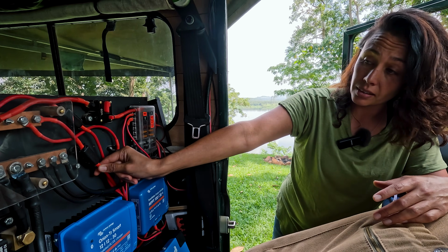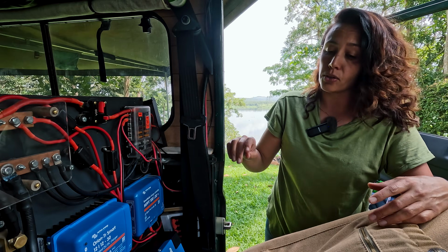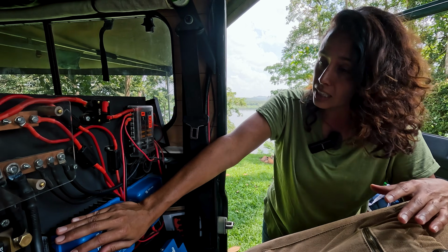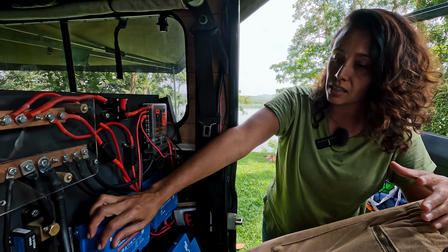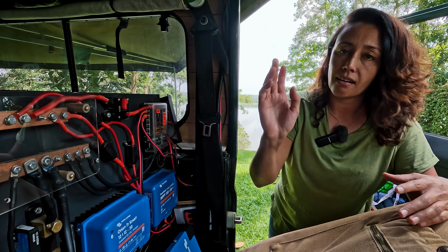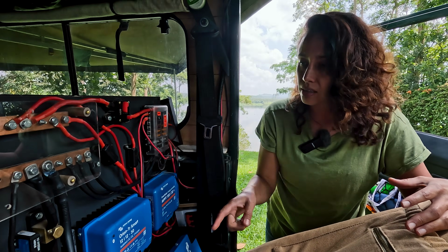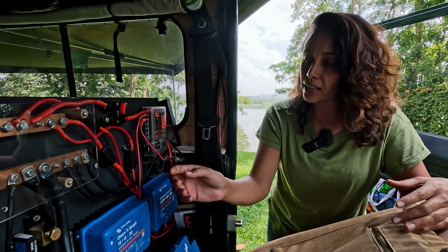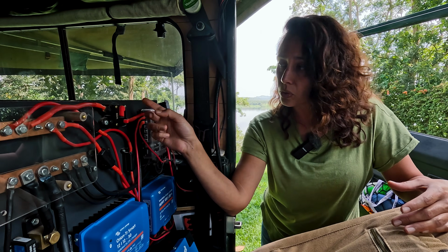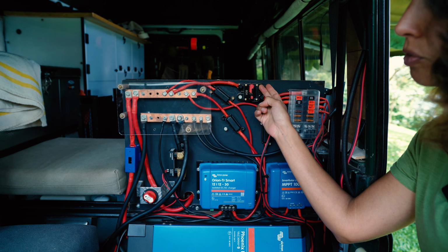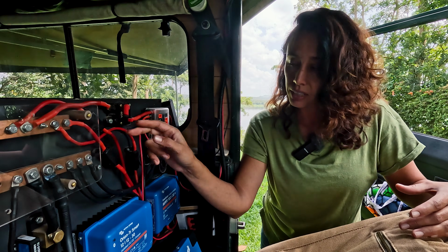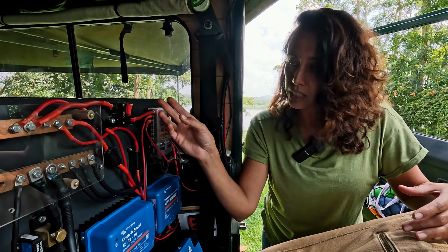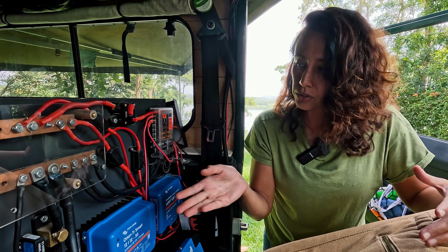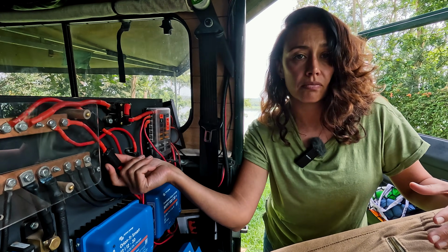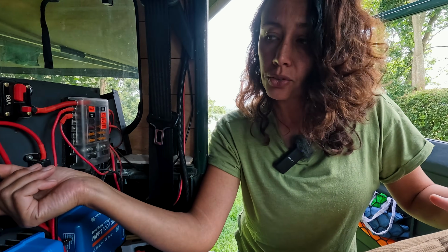I would not recommend these circuit breakers, because we thought this thing was broken, since it would charge for a few seconds or a few minutes and then nothing happens, and you can see the signal just dropping. Finally figured it out, and it was the circuit breaker that was just overheating. Even though it's a 60 amp circuit breaker, it's overheating, switching off, and then you lose the signal. So we just swapped it for a fuse.